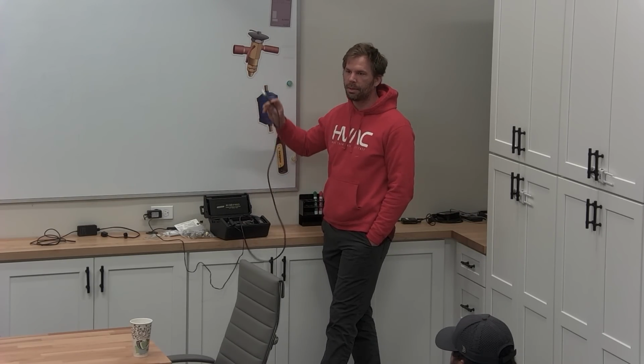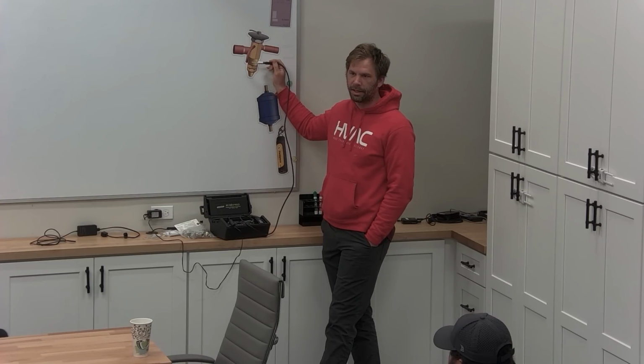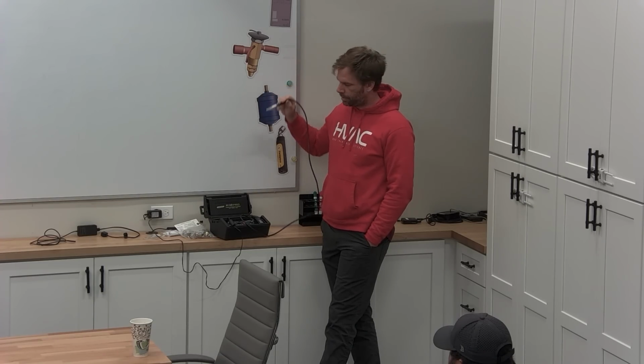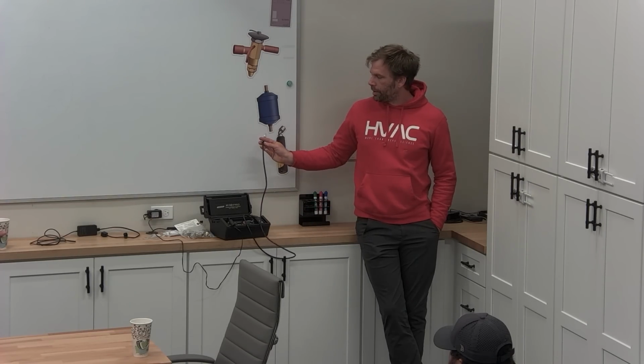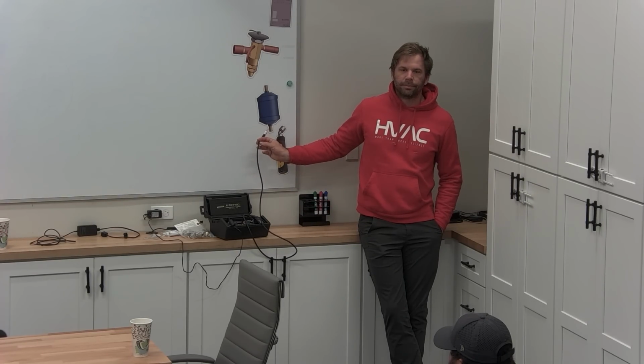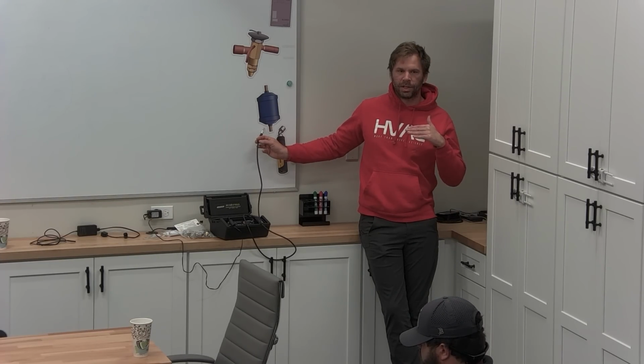We've talked about this many times, confirming a leak, going back to the air and coming back and confirming that leak again. Part of that is you could have it in auto mode, and it could potentially have calibrated. You put it straight to where your most likely leak spot is, and it could have got a big hit and then stopped because it recalibrated to that level of refrigerant.